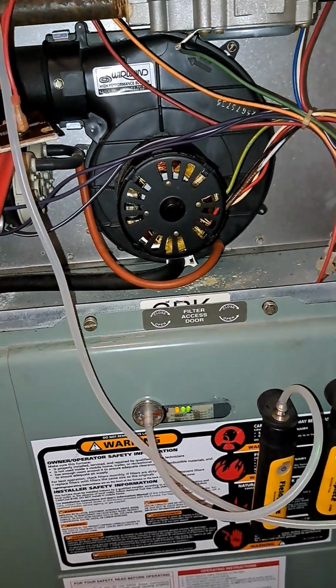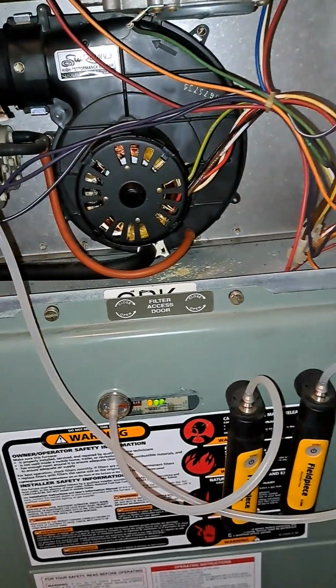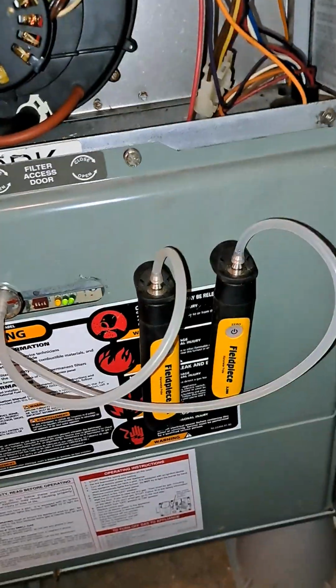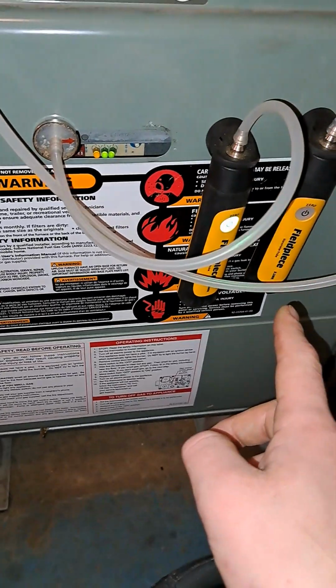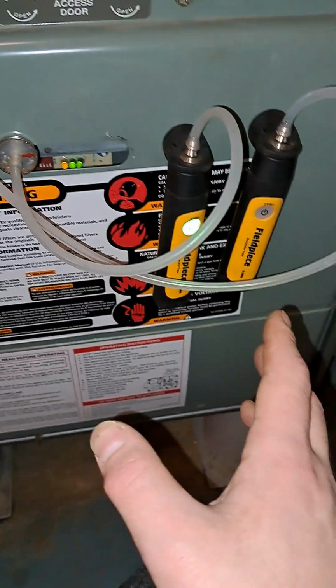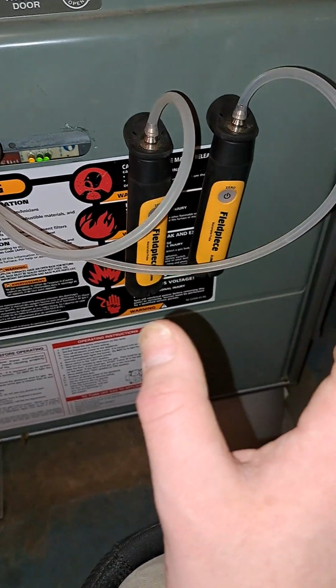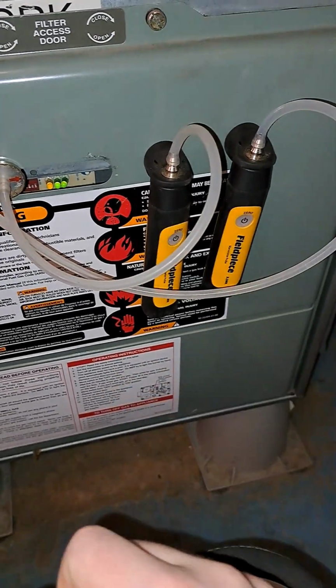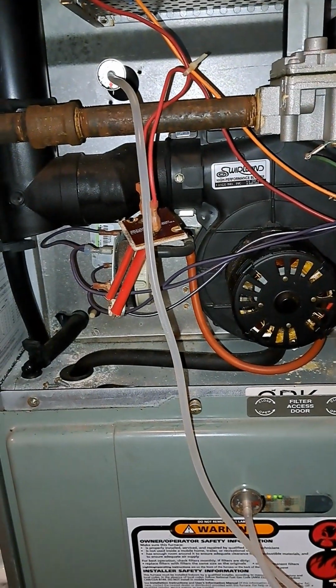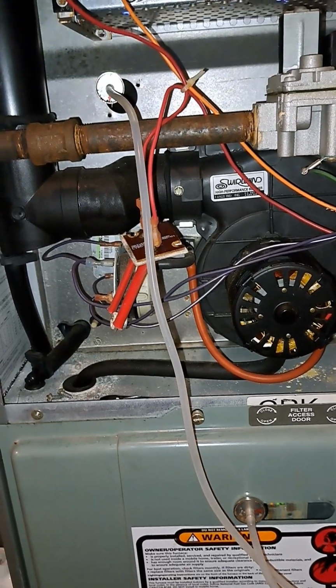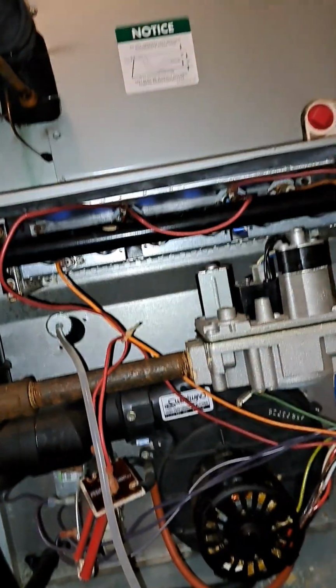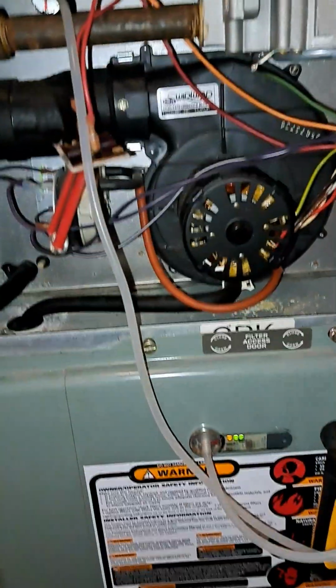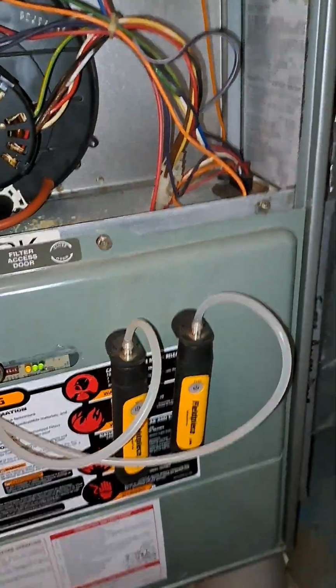Another thing that's handy is looking at each reading separately. If my negative side is higher, that means I have a restriction somewhere on my return. If our positive side is higher, that means we have a restriction in our supply somewhere. That could be anything from a bunch of registers closed, too small ductwork, a caked coil—and with the return, the same thing.